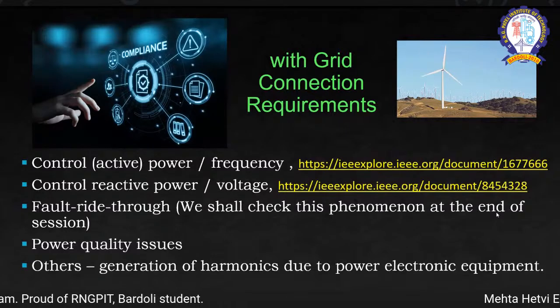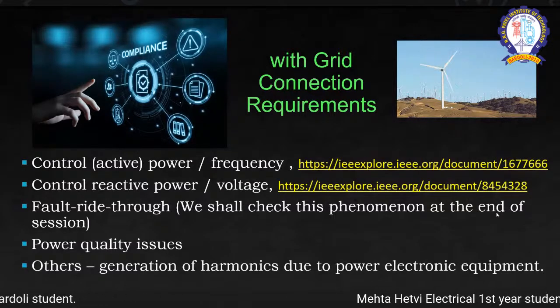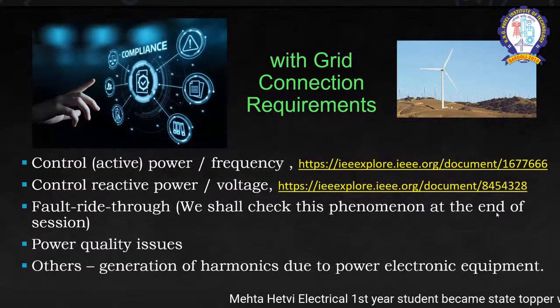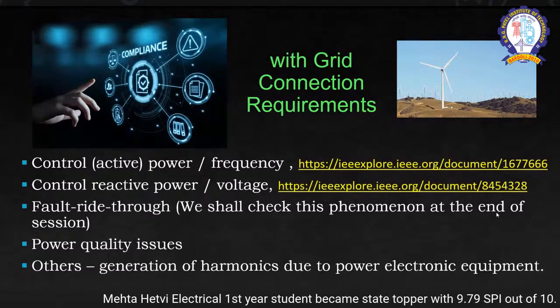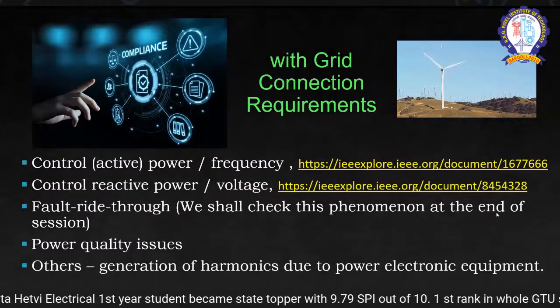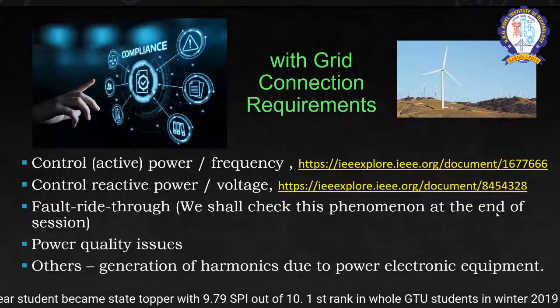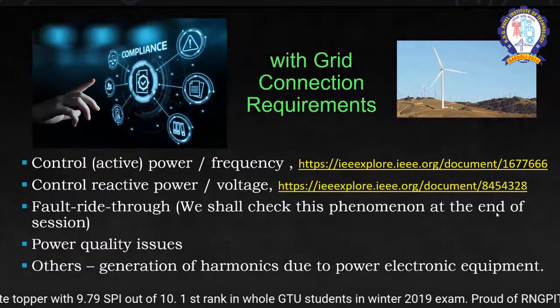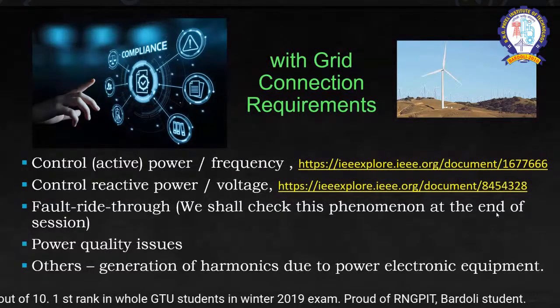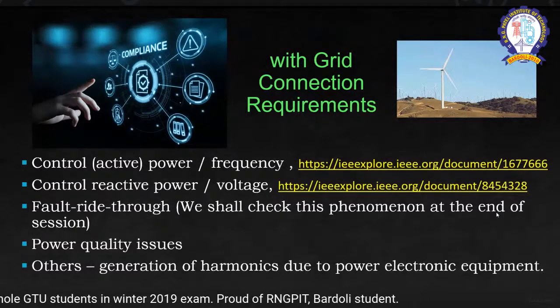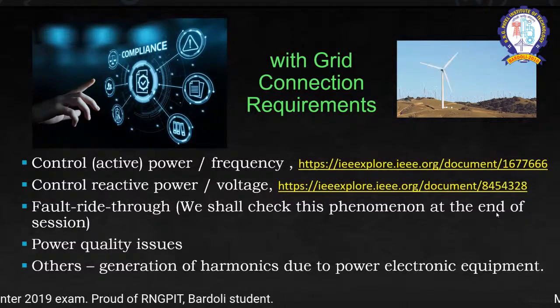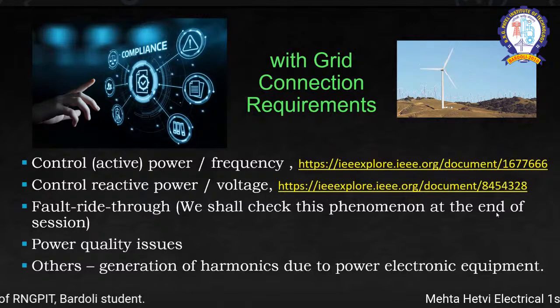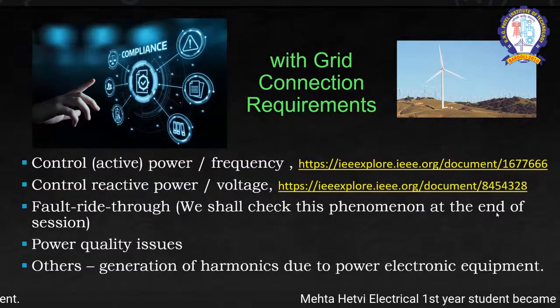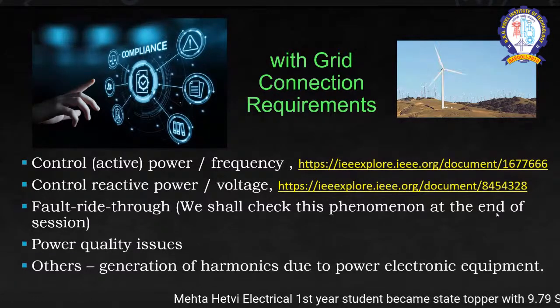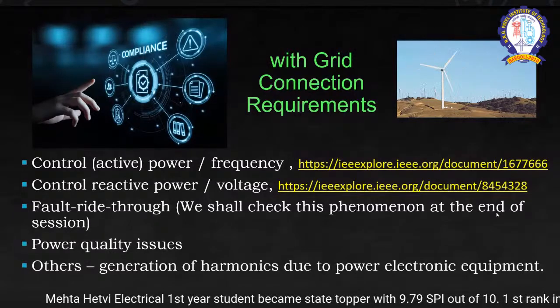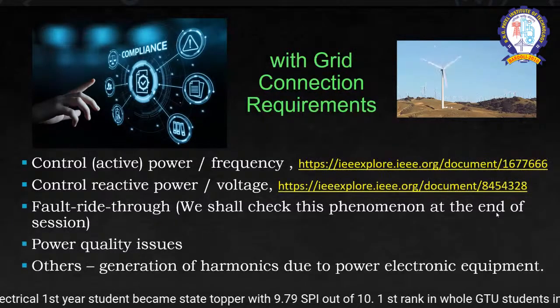The third, and most important, is fault ride through. It is also known as LVRT, that is low voltage ride through. It is also known as fault ride through. When there is a temporary or transient fault in the grid, at that time the grid will collapse and again regain. So the current situation says that our wind turbines must be FRT enabled or LVRT enabled.